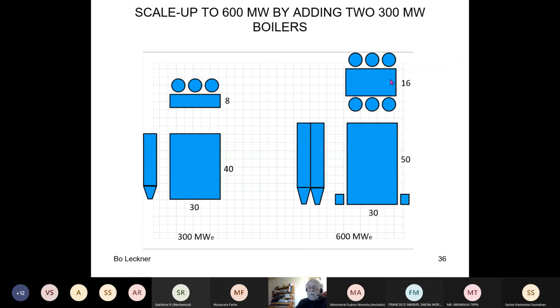They could add a few internal wing wall surfaces, and then they could add some wall surfaces in this central part of the furnace, as I have shown before, and as is maybe indicated here. But the amount of heat transfer surfaces in the furnace was not enough. There was not enough space.